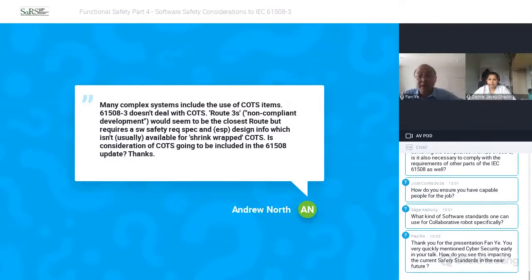If you have an adequate, very robust data gathering and recording system, Route 2S and 3S can be used. In the next edition of 61508, Route 2S will be significantly expanded, precisely for the reason of the example given in the Ariane 5 accident, where you reuse previously successful software that caused a catastrophic accident.